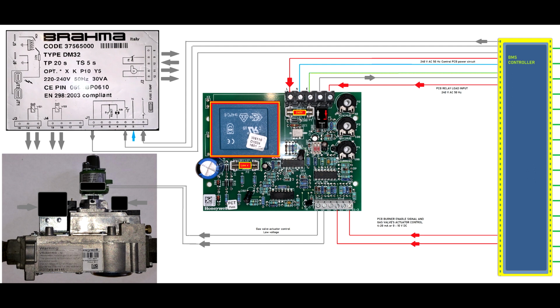So now if you look at the lower side, I enabled this printed circuit board. I provide as an example 5 volts, or somewhere in between 3 and 10 volts, and when I did this, automatically the control capacity to the gas valve became active, and at the same time another signal from the printed circuit board goes to this relay, and if you look now, the relay is active, and it sent back the signal to this building management control. Please be aware that that signal can go directly into the Brahma controller, into the burner controller. It is a choice. It's how much you want to monitor the health status of your heating system.